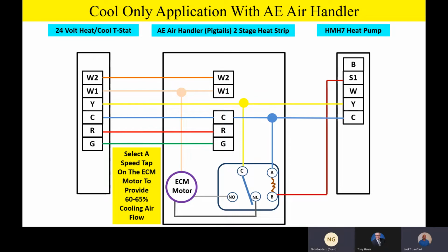So let's say for instance, you're absolutely stuck with 2 wires outside and you just can't get another wire out there. You can not worry about installing that relay. And you see that yellow wire up there that we're going to the common terminal on the relay. You can take that yellow wire for compressor operation and take it right over to your 100% airflow speed tap on your ECM motor, and eliminate that relay altogether. You take that yellow wire on the common terminal of the relay and just take it over to your 100% airflow on your ECM motor, and then you'd have 2 wires going outside.